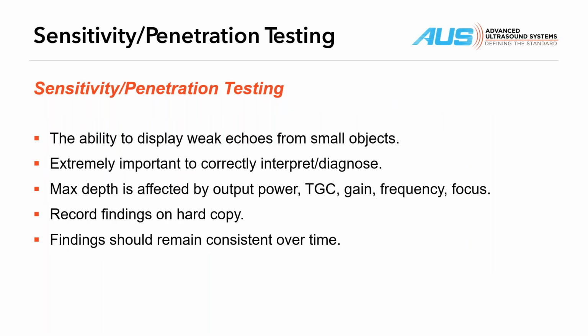Findings should remain consistent over time. What you're looking for is degradation over time. That's what the preventative maintenance is all about as far as the image quality portion of it goes. We're going in there and we're evaluating the system to see if anything's changed over time. So it's important for us to have pictures from the last PM and compare them to pictures of this PM and see if it's consistent, see if our penetration testing is resulting in similar results. If we were penetrating to 10 centimeters in January and we can only get to 6 centimeters in July, well, clearly something has changed over time, and now you have to go in and do some investigation and find out what has changed over time and correct the issue.